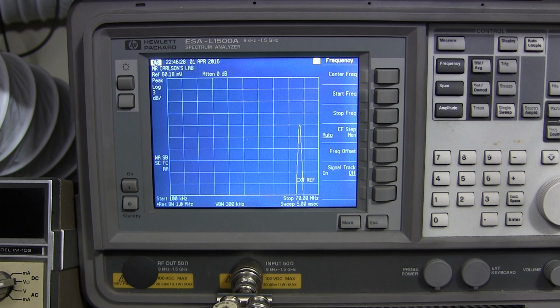So right down here, that's considered the 3 dB down point, and that's at 61. I'll just fine tune this here. So 61.300 megahertz or around that. I have this working at 100 kilohertz, moving it in 100 kilohertz increments. So we could comfortably say around 61 megahertz would be the top end of this probe, and again, that's at the 3 dB down point.